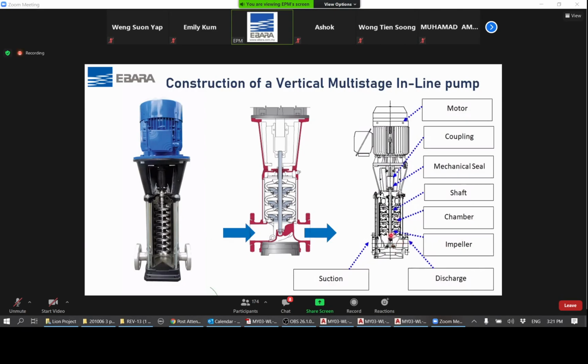So basically, for such a pump, the higher pressure you need means there are more stages. Okay, so you can see some pumps are very, very tall, and that could mean that it is a very high pressure pump. Now, one of the advantages of this pump is that it can deliver more than 20 bar at its maximum stages, depending on the model chosen, and is suitable for even the highest building all over the world.